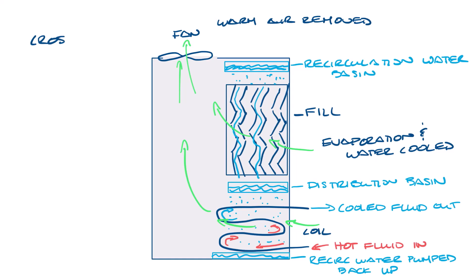Like cooling towers, fluid coolers can be either cross flow or counter flow. In cross flow, the air comes in from the side and moves across the coils perpendicular to the direction of the recirculating water. This is basically what I just drew.